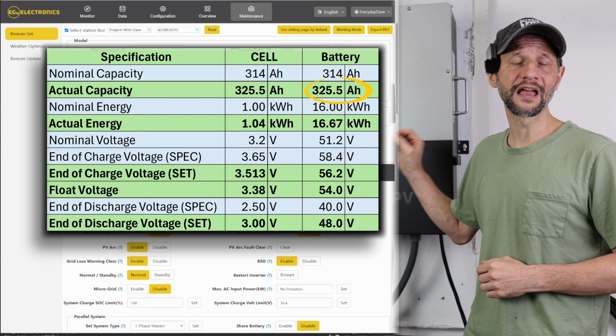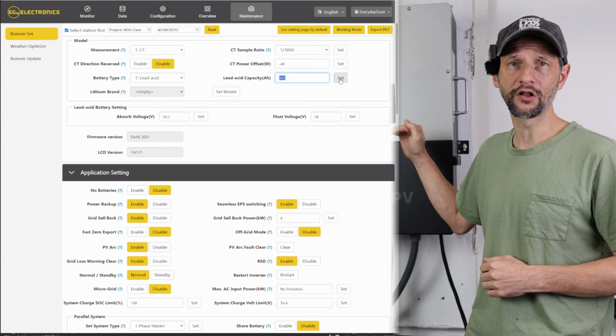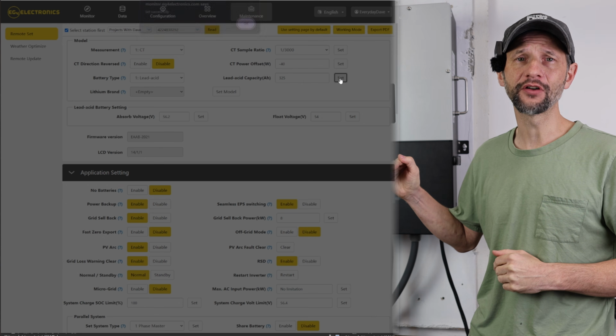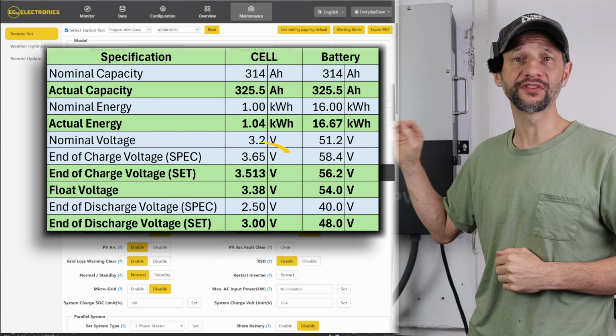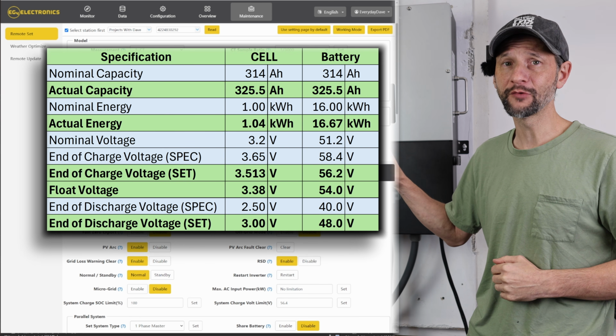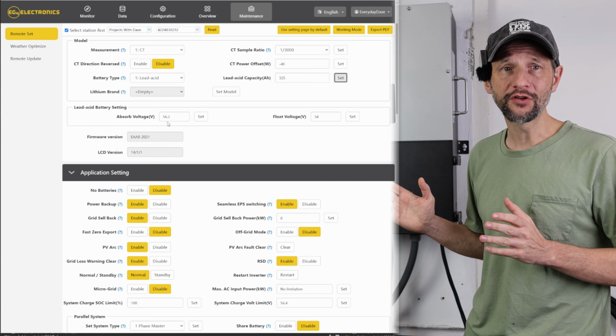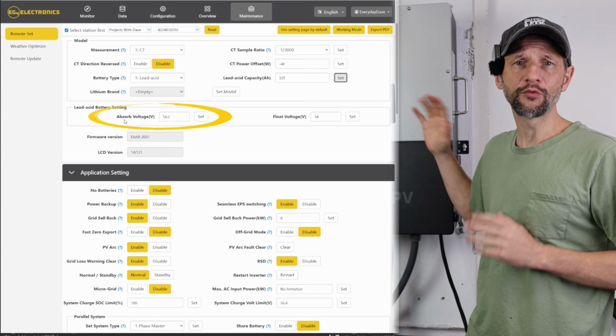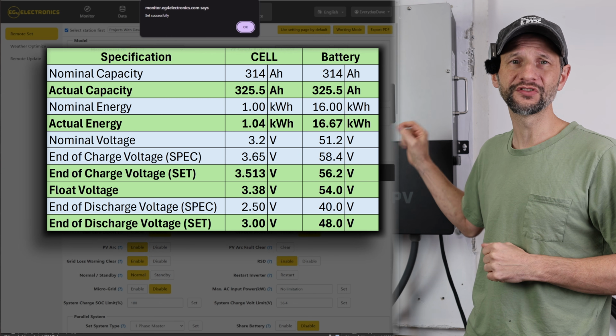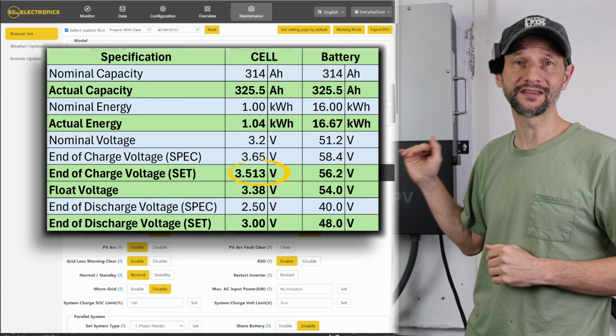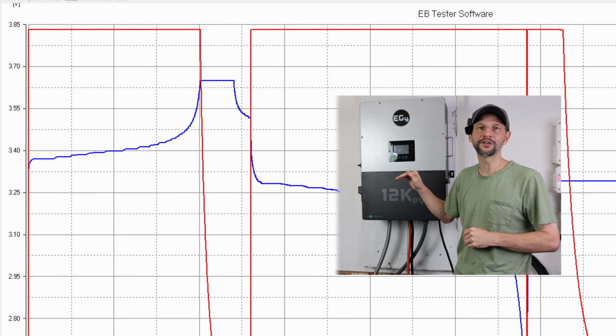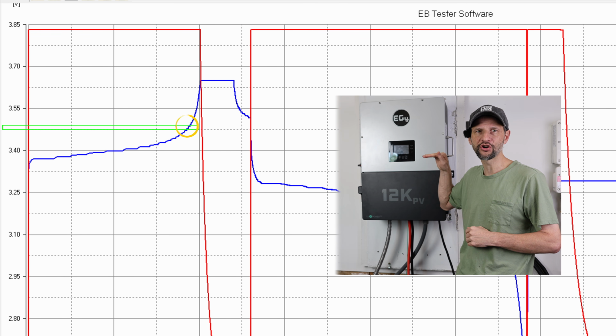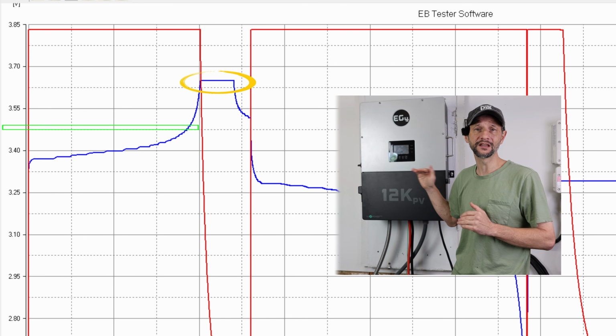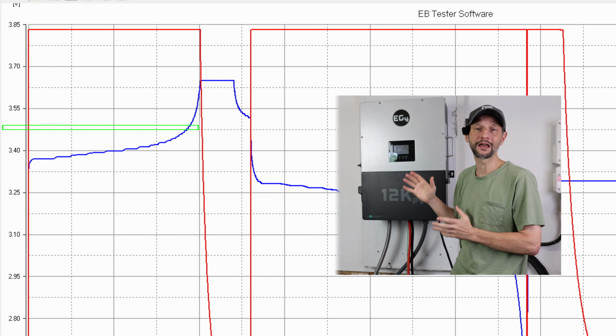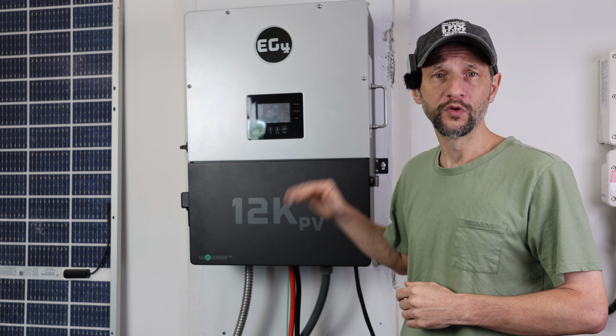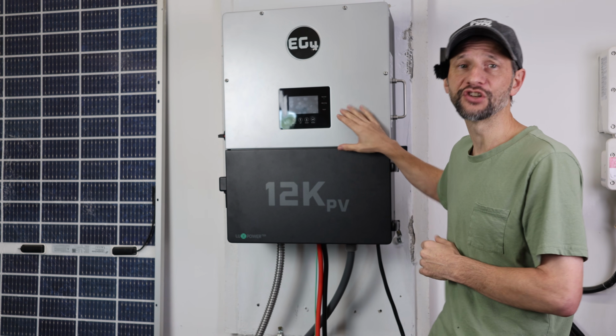My tested capacity was actually 325 amp hours, so I'll enter that in the capacity line. The spec sheet calls out an end of charge voltage of 3.65 volts, which is what we set the maximum voltage in the BMS. For the battery pack, this is the absorb voltage, and I will set that to 56.2 volts, which is an equivalent of about 3.5 volts at the cell level. On the battery charging curve, you can see that this is well above the flat part of the charge curve and below the maximum setting in the BMS. Running at the extremes of the curve reduces battery life. We accomplish two things with this setting. We increase the battery life, and we keep the inverter in charge of the charge cycle.